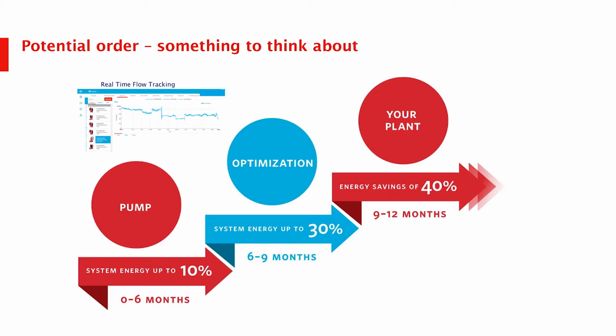I'd like to challenge the people in the room, though many already implicitly agree, that pumps are a logical place to start, squeezing out the inefficiencies that exist in the system before deciding what else to replace. You might need a new cooling tower, a new chiller, or to repipe the mechanical room, but see what you can get out of your existing system before making that decision. The people in this room might not make that decision themselves, but you certainly have influence.